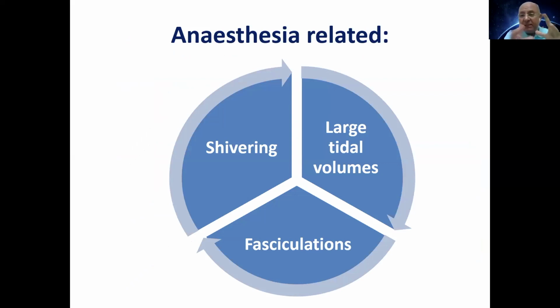Shivering, the myopotentials of shivering and also of fasciculations, will be sensed by the pacemaker or by the ICD. For the ICD, it will be sensed as tachycardia or as VF, and it will give an inappropriate shock for no reason, which is, as I said, very harmful and very painful to the patient. If a patient is pacemaker dependent, it will sense this activity as R waves, as contraction. So it will not pace the heart, it will not pace the patient.